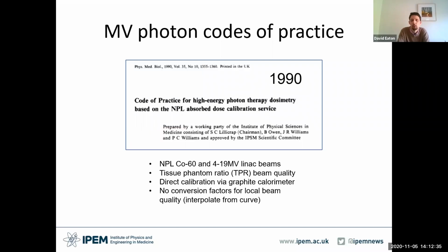But for the most part, it works pretty well in terms of defining a beam in terms of a single number. And this code of practice was quite revolutionary in that instead of relying on exposure factors and conversions from exposure, it involved a direct calibration of absorbed dose. So using a graphite calorimeter to measure temperature rise and then converting that to dose to water in the chamber that was being compared. So the real hallmark of the NPL and UK IPSM code of practice is that it doesn't require conversion factors for all the local beam qualities.